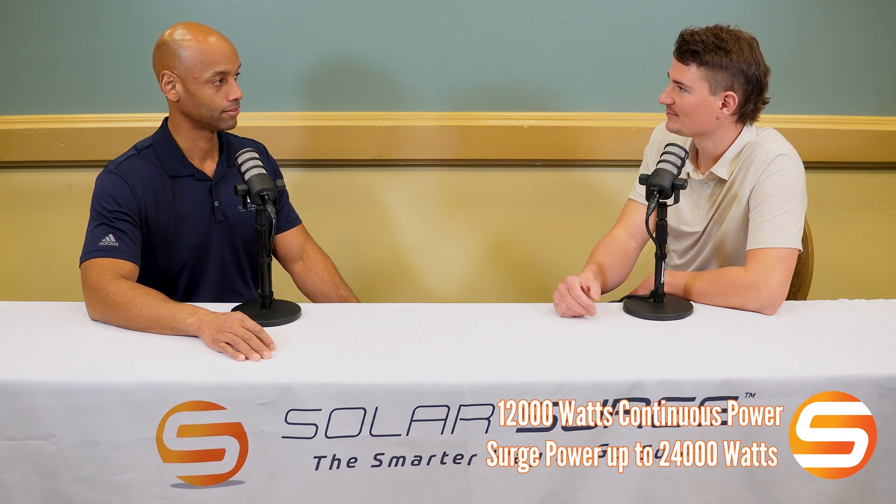I think that was actually probably the first thing that got my attention. For those of you that follow me closely, I have a solar system in my home — I have the 5k single phase, not the 15k. But the Solar 15k — what caught my attention was this is the only battery that will allow the Solar to run at max power with all of it coming from the battery. The Solar Edge battery is 12 kilowatt continuous on the 15k, and then a 24 kilowatt surge, which almost pairs up exactly with our battery. The benefits are just that we can do full home backup — we can turn on a five ton AC, your well pump, your pool pump. That's what most homeowners want. If you're going to invest $15,000 to $20,000 and it only can power your fridge and lights, that's semi-frustrating. But if you're your own power plant, your own micro grid, and you're not relying on the grid — if they raise the rates, you don't care, because you're grid independent. If power shuts off and your lights don't flicker and your jacuzzi still runs, it's pretty exciting.